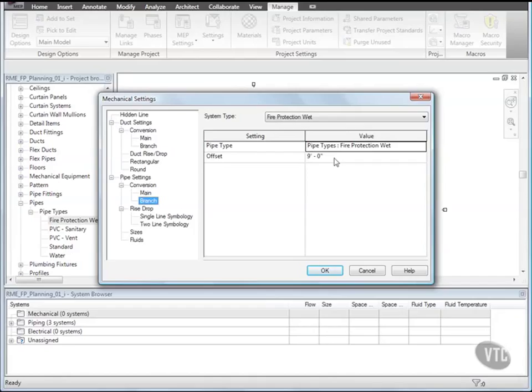This is useful for avoiding interferences with pipes, ducts, structural beams, or architectural components. It is good to note that Conversion Settings are applied when you convert the Piping Layout Path to Physical Piping. You can configure the Conversion Settings at the beginning or during your project. However, you should configure or verify the Conversion Settings before you convert a Layout Path. Configuring the Conversion Settings is usually a one-time process unless you need to change them during your project.